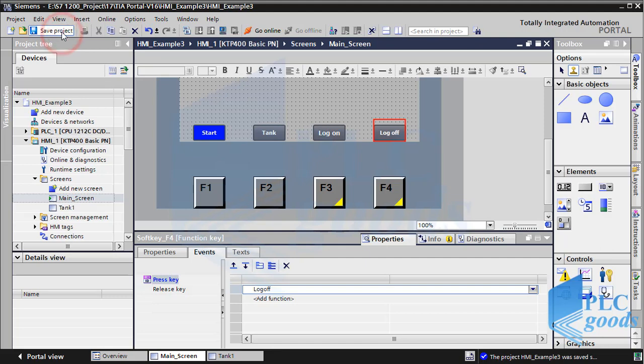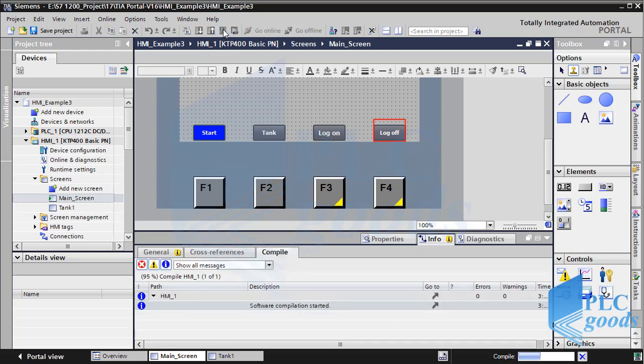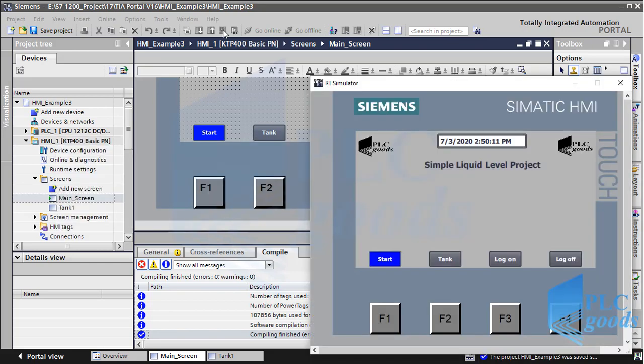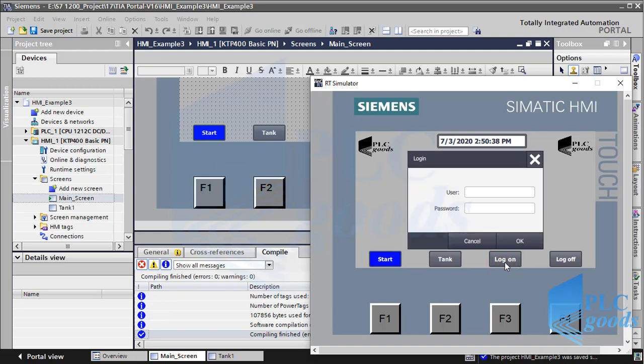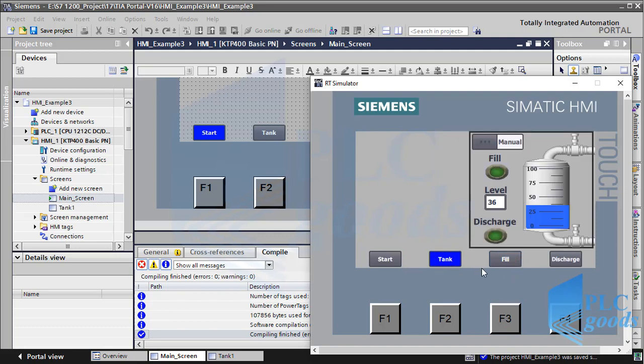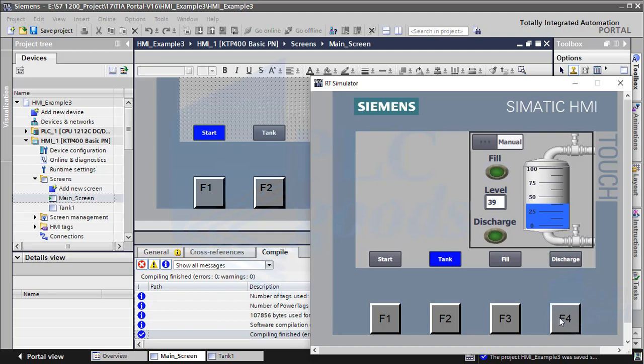Now let's test our HMI screens. The log on button and the F3 key open the login window on the start screen. In the tank screen, the F3 and F4 keys can be used to fill and discharge the tank. So F3 and F4 keys have different tasks in each HMI screen — this way of using function keys is called local assignment.